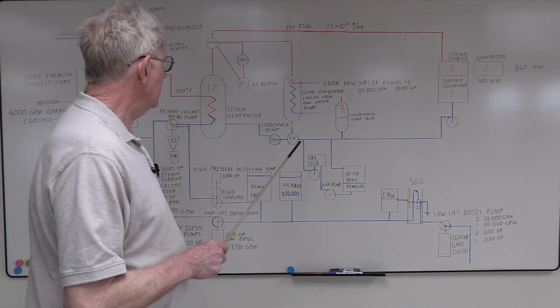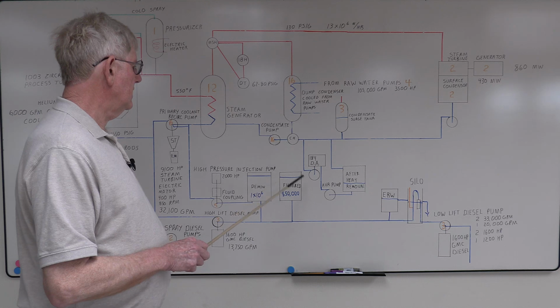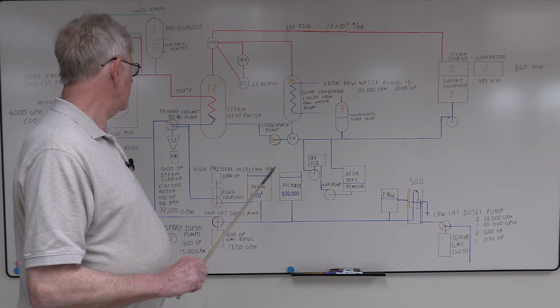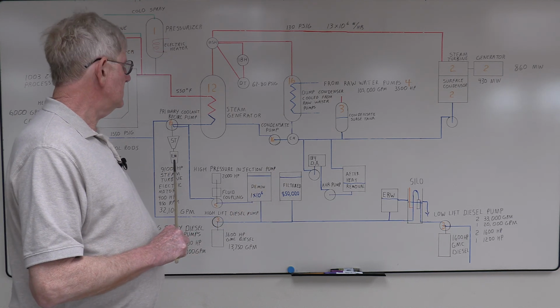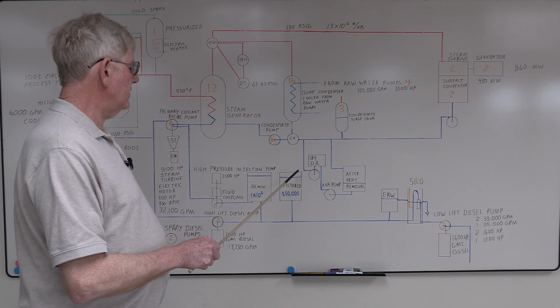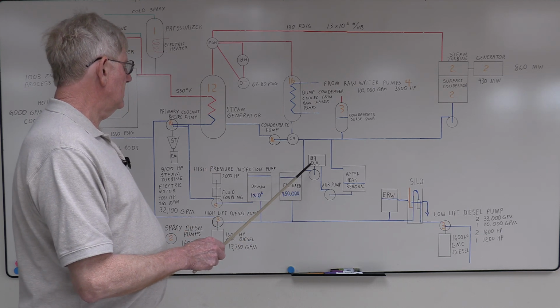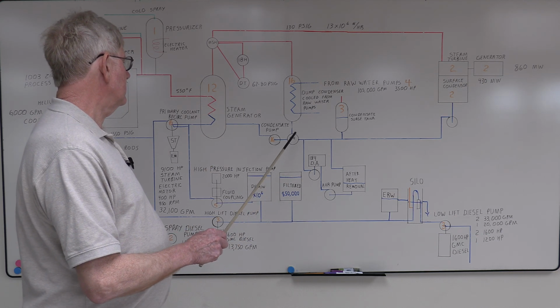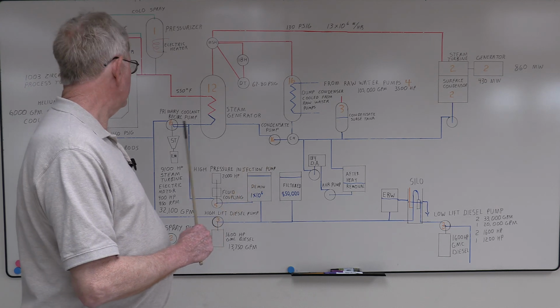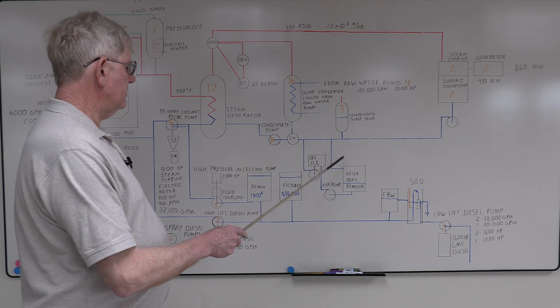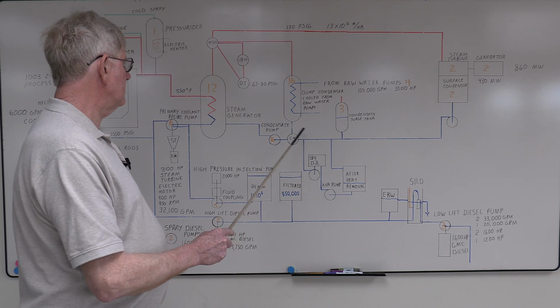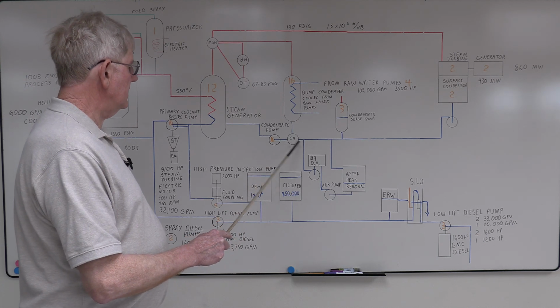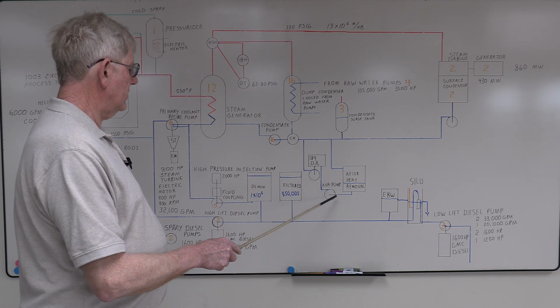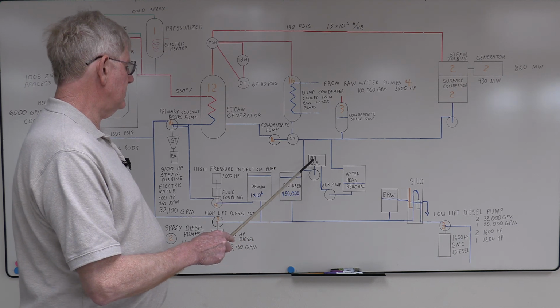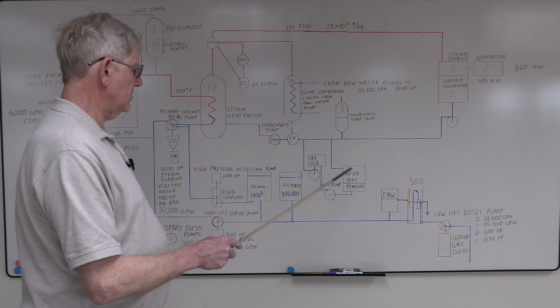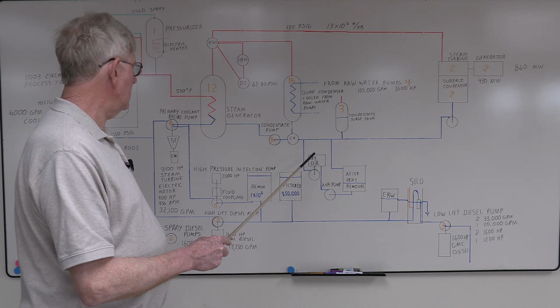Another thing in the powerhouse had the deaerator. All the return from the steam turbines and your turbine generator went back to the deaerator, and also all makeup water fed through the deaerator for your condensate header. Your after heat removal tank dumped water from your condensate header and provided water to your after heat removal pumps, which fed the deaerator if the level got too low. You had normal makeup to it.